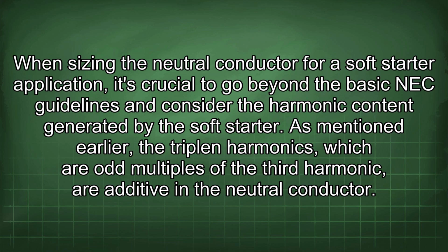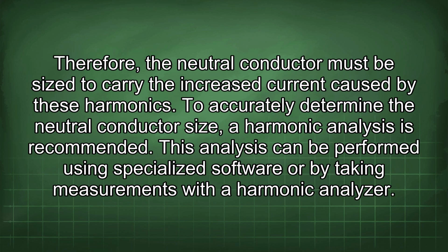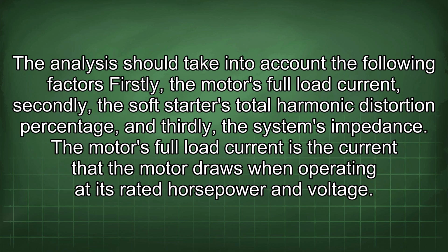As mentioned earlier, the triplen harmonics, which are odd multiples of the third harmonic, are additive in the neutral conductor. Therefore, a neutral conductor must be sized to carry the increased current caused by these harmonics. To accurately determine the neutral conductor size, a harmonic analysis is recommended. This analysis can be performed using specialized software or by taking measurements with a harmonic analyzer. The analysis should take into account the following factors: firstly, the motor's full load current, secondly, the soft starter's total harmonic distortion percentage, and thirdly, the system's impedance.